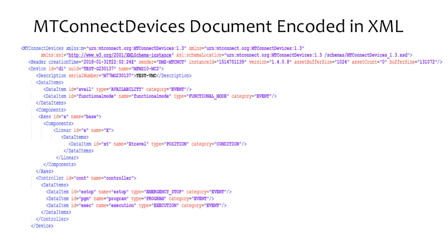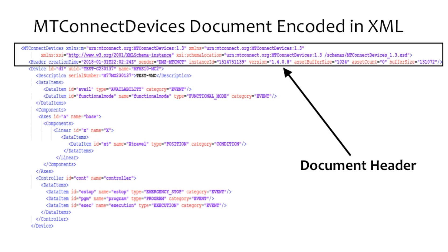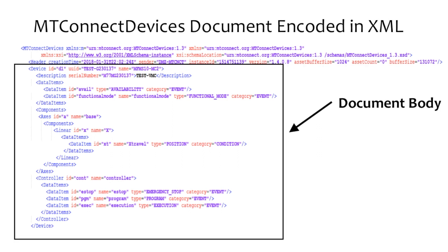XML represents information in a structured text format. The topmost portion of the document is called the document header, which contains two types of information: information used by a client software application to properly interpret the contents of the document, and additional information that a client software application needs to know about the MT-Connect agent so that it can make successive requests for information. The document body contains the information a client software application needs to know about a piece of equipment and the data to be reported by that equipment. The client software application uses this information to fully interpret data published by the equipment so that it has the same context and meaning that the data represents on the shop floor.